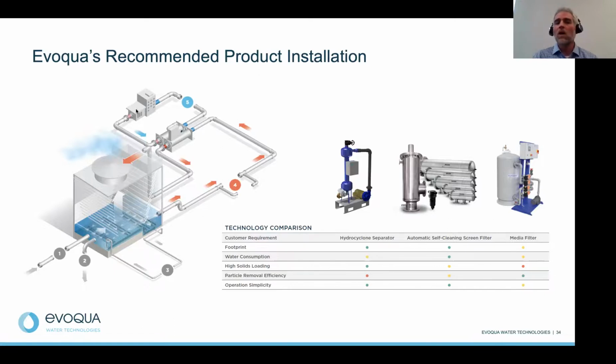Work with your chemical provider, work with someone who can test your cooling water, and understand where your solids loading is arising from. Is it makeup water? Are you focusing really on the basin? Is your closed loop having high iron excursions because of dead legs? Understand your cooling tower, understand where your solids loading is, and understand the particulate size that is in your cooling system. With that in hand, you can ultimately then work with Evoqua staff to select your best solution, depending upon the operational requirements, but ultimately what your goal is at your site.